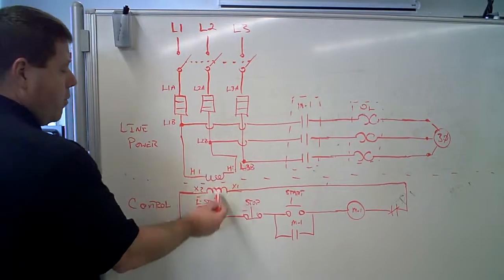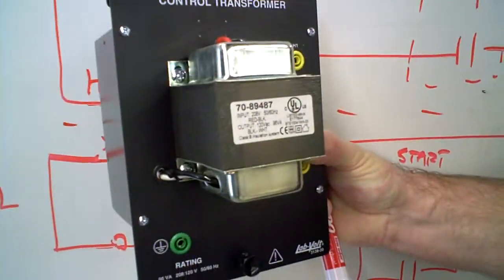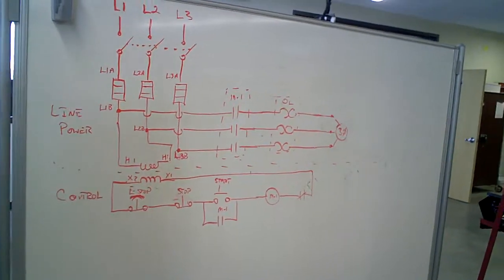It's not a problem. So the transformer here, which is this device, the transformer sits right here, and it separates the two systems. So basically your control circuit is a separately derived system off of your primary. So you get that step-down voltage down to 120.